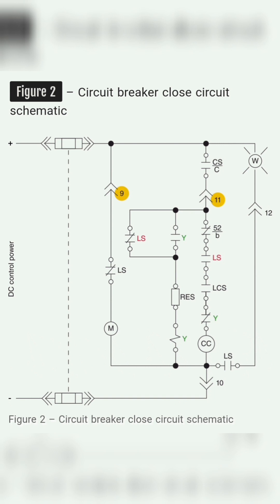What resets the Y relay is the removal of the close command from the control switch contact CS-C. The normally closed contact from the Y relay is then closed because the anti-pump relay is no longer powered. Stab pin 11 receives voltage when the control switch close contact is closed. The close coil is energized when the 52B contact, LS contact, LCS contact, and Y contact are all closed. The 52B contact automatically opens when the breaker closes, cutting off power to the close coil.